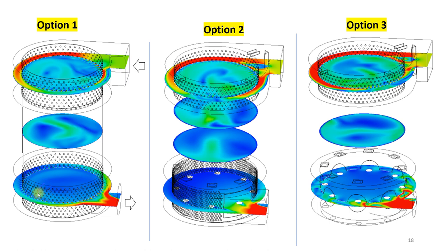At the bottom hole, the fluid flow is distributed uniformly due to the circular hole, but it adds more resistance to flow around the circumference than the outlet. That means the flow path is longer. It passes through a circular hole, then it flows through the annular passage, and then it takes more resistance, because all this accumulation of fluid here takes time, and these perforated holes are also adding resistance to flow.